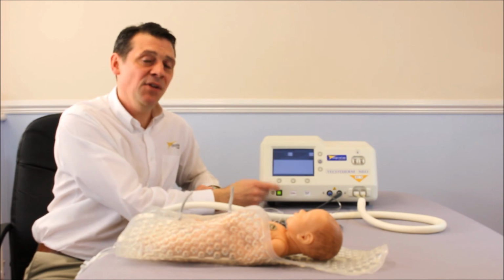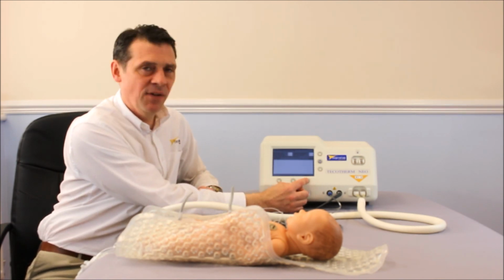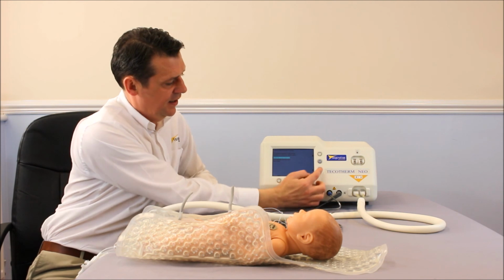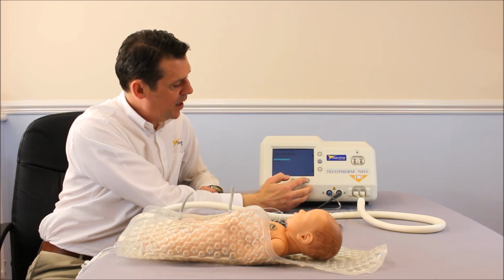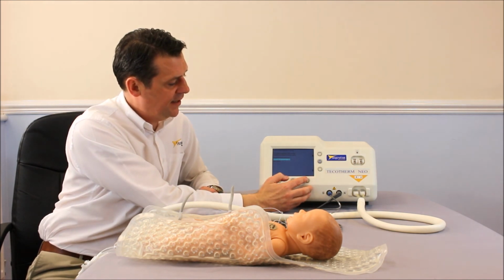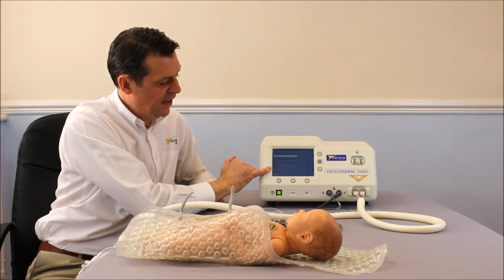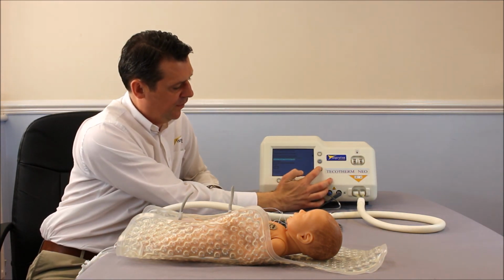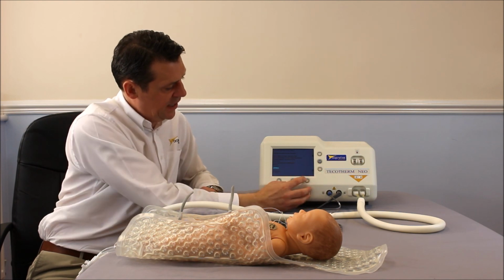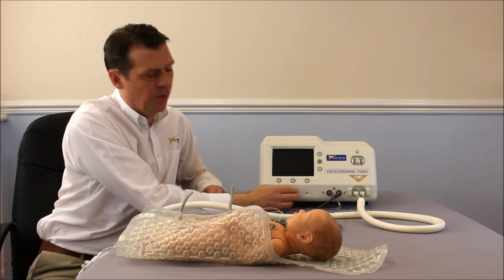To switch the machine off, I'm not able to switch it off from the front button here. I have to go through a small process. If I go to options on the bottom right, bring the light blue box to end treatment and save data and press select. That will bring up a new set of menus, and at the bottom there is power off. If I bring the light blue box all the way down and press select, it will then switch off.